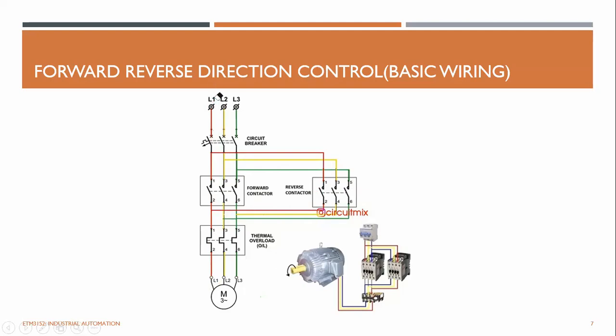And now you can see here, this one, the L2 now comes from here, and it goes to L3, right? It goes to L3, not to L2. And this one, L3, now it is coming from here and goes to L2. So you can see now L2 and L3 are swapped while keeping L1 the same, which means the direction is changed. Okay.